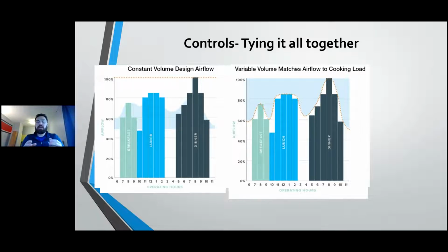So basically, what is that doing? It's sensing the temperature under the hood. If you turn all your appliances on, that's going to generate heat. That heat generation is going to bring you above your ambient temperature, and that's going to signal to the exhaust fans per the temperature interlock that, hey, we now need to start the exhaust fans and interlock the exhaust fan with the makeup air fan, regardless of if the chef has turned the fan switch on or off. If it's sensing temperature, it's going to start that fan.